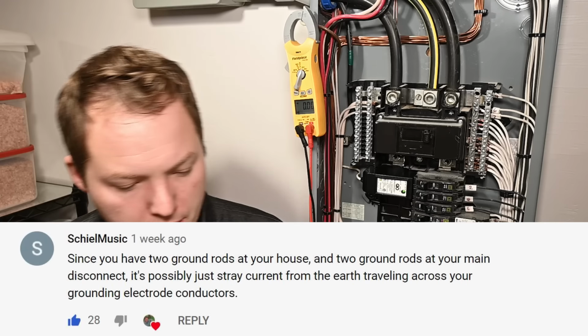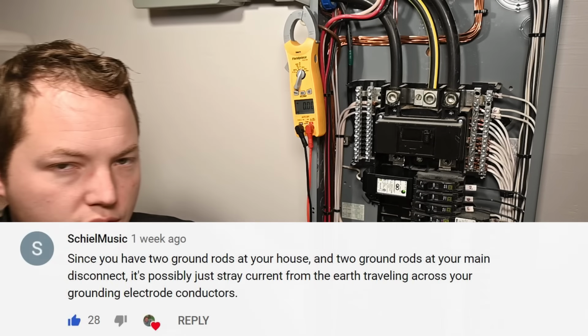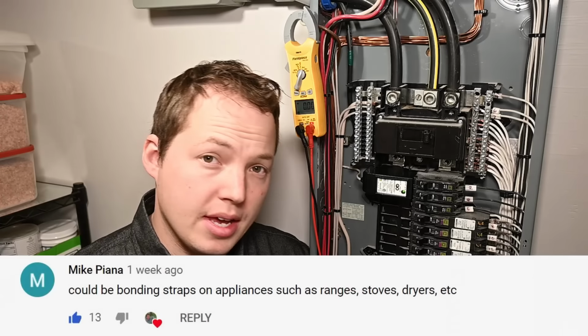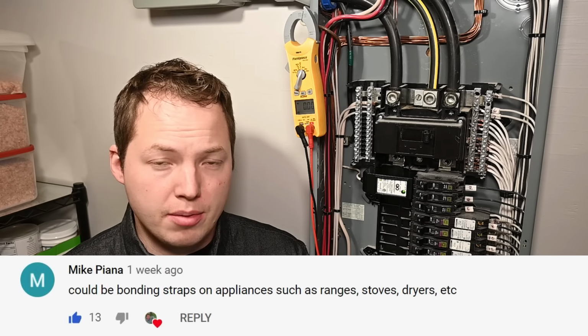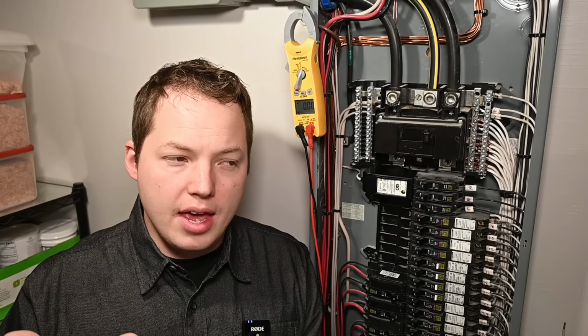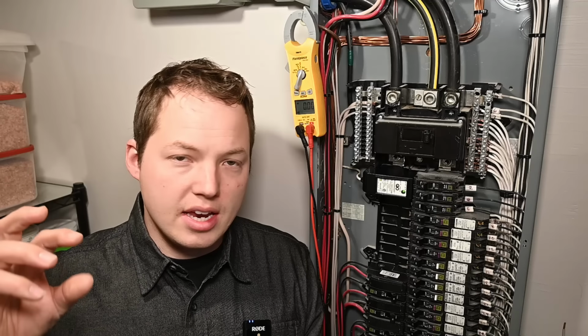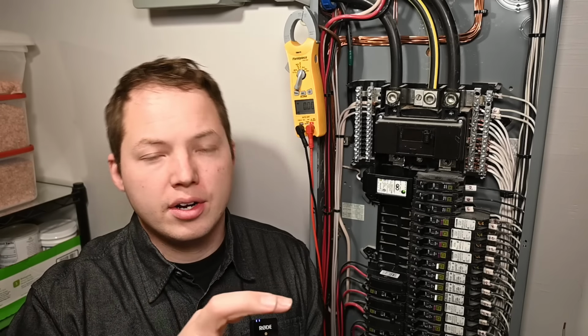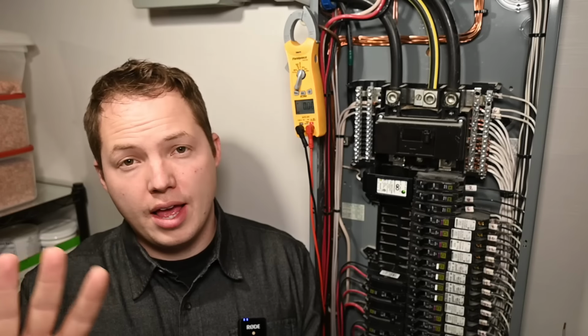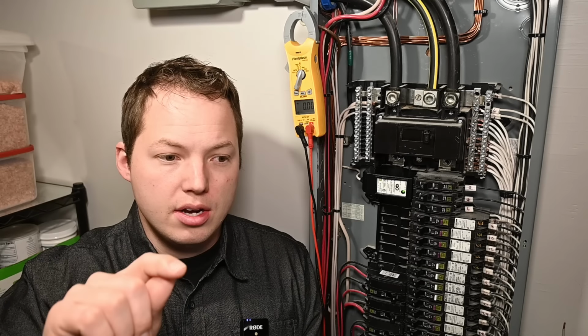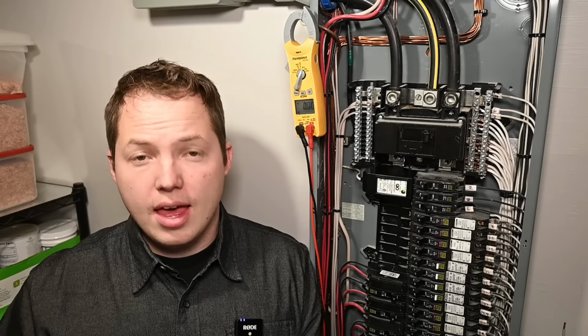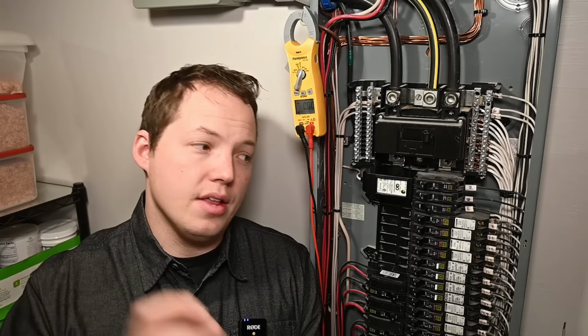Now this is a super interesting one: difference in potential between two sets of ground rods. Now a bonding strap being connected in an appliance is another possibility. That could be like a dryer or an electric range, where they are designed such that they can be used with a 3-wire cord or a 4-wire cord, and there's a bonding strap that connects the neutral and ground inside of that appliance. If that was not removed, then you could see the situation where some of the current is going back on the ground wire.